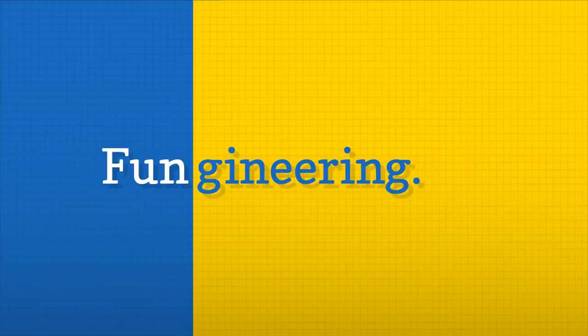So you have two things when you first start inserting the control rods that both cause the reaction to speed up. And so the reaction has already started to get away from them because the water flow is too low to cool the reactor enough, and they've removed too many control rods manually. And they've done this test in a configuration where a lot of poison was built up, ready to get burned off and cause the reactor output to increase very quickly. So they've created this incredible confluence of conditions that causes the thing to just run away once they start putting the control rods back in.